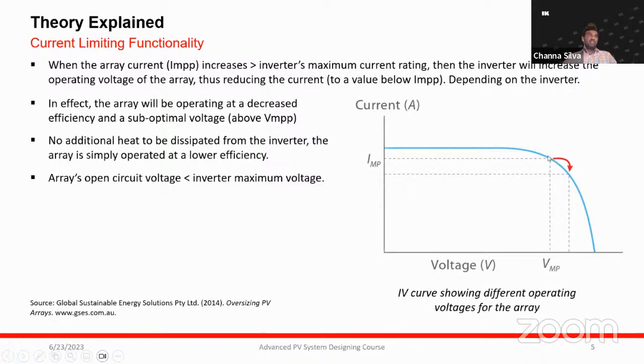So the inverter's maximum power point tracking algorithm always tries to find the instantaneous maximum power point, which represents the maximum power point current and maximum power point voltage. But let's assume that this particular inverter is trying to track the maximum power point from the array itself. Let's assume that the maximum power point current is greater than the inverter's maximum current rating. What is going to happen?